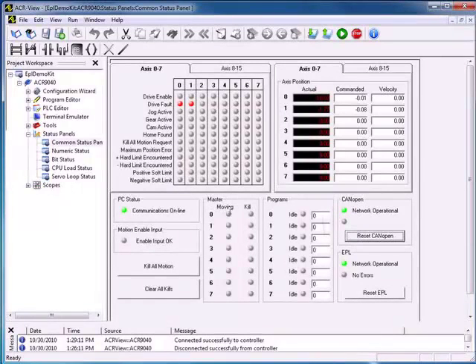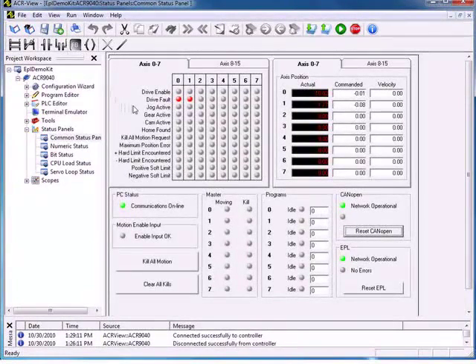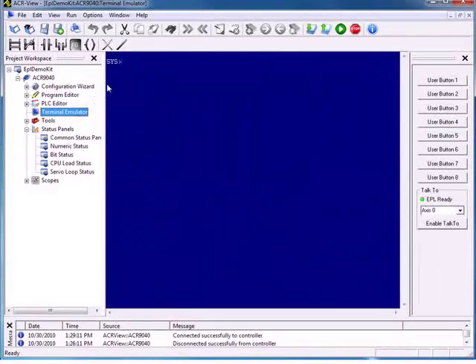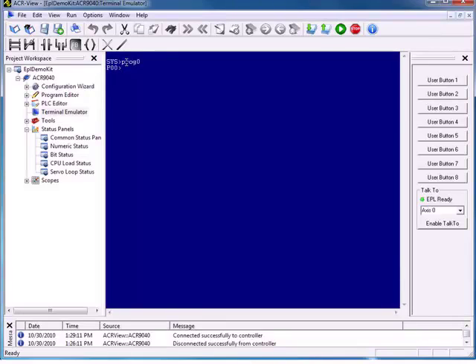As long as there are no hard faults or configuration errors, I should be able to clear my drive faults by turning on the two drives. To do that, we're going to go to the terminal emulator. To enable my drives, I am going to switch to PROG 0. In order to turn on the drives using their aliases, I need to be in the program associated with the master they are assigned to. Since these drives are assigned to master 0, I need to switch to program 0 to turn them on by their aliases. I'm going to do a drive on X and a drive on Y. I could have done a drive on X Y here as well.